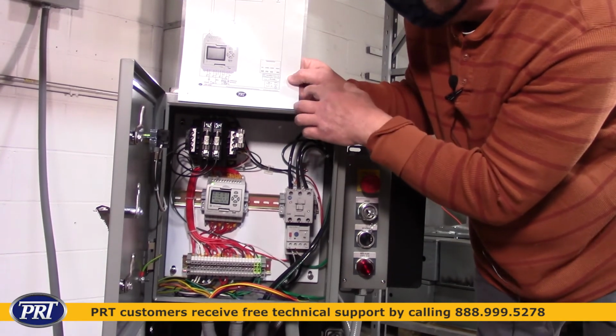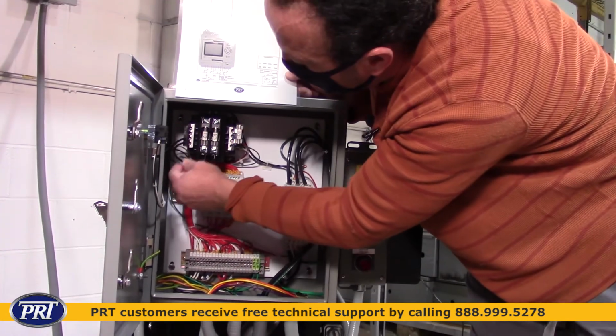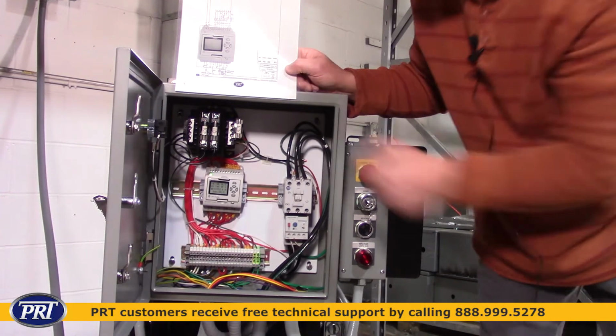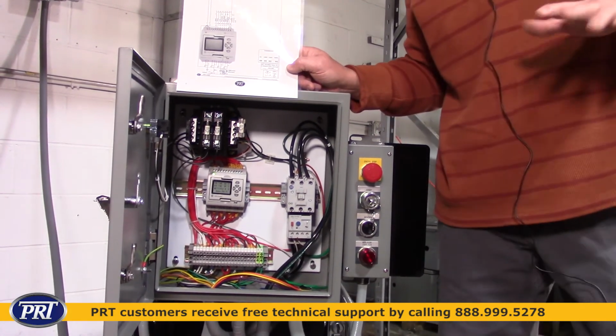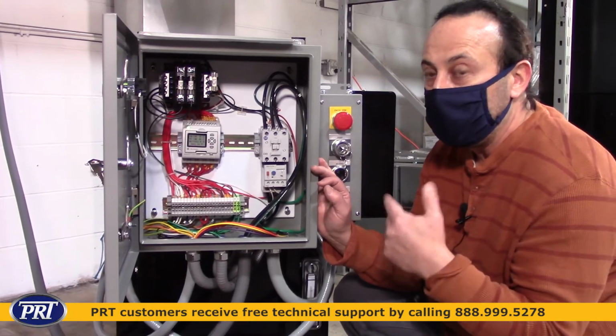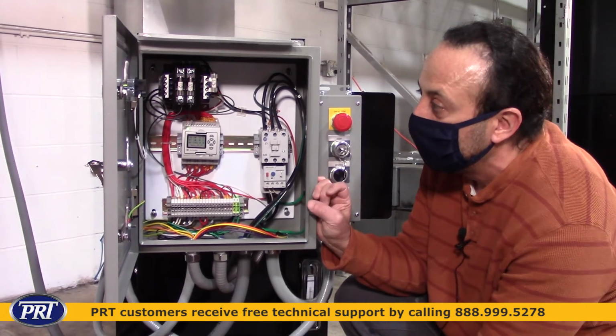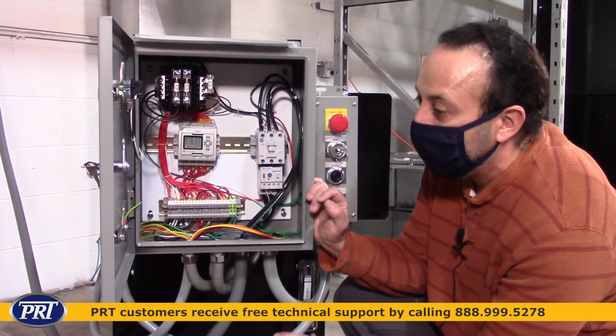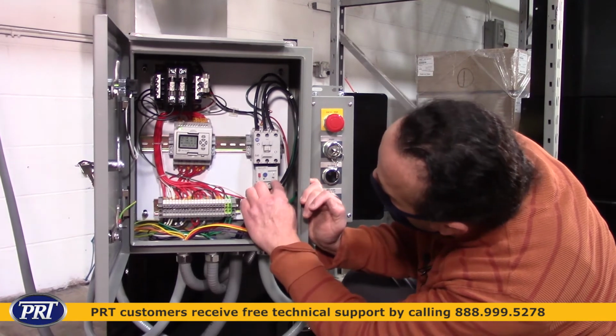If I want to go to high voltage, then I would take that wire that's on number 4 and move it up to H1, and that would convert it from low voltage to high voltage. And the final thing that you have to adjust when you're swapping your voltage over from high to low or low to high is the overloads down here.